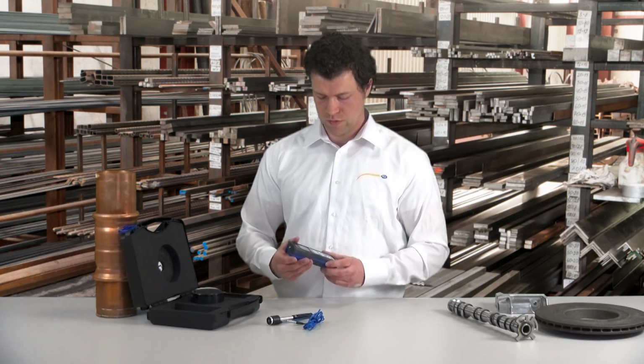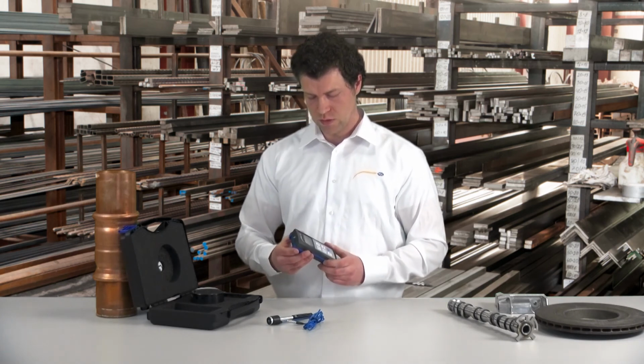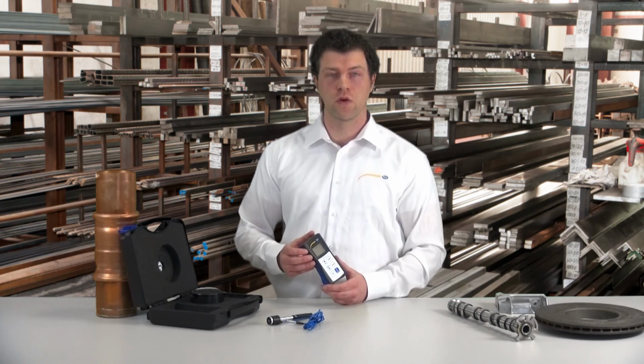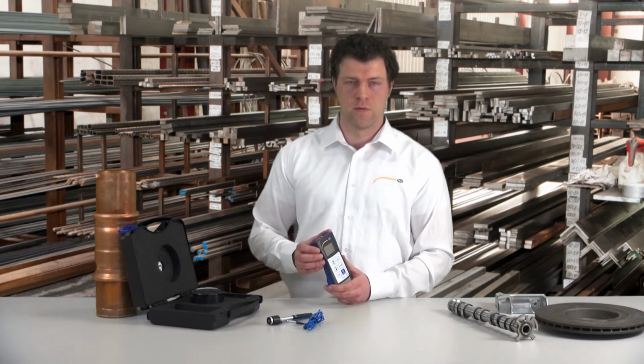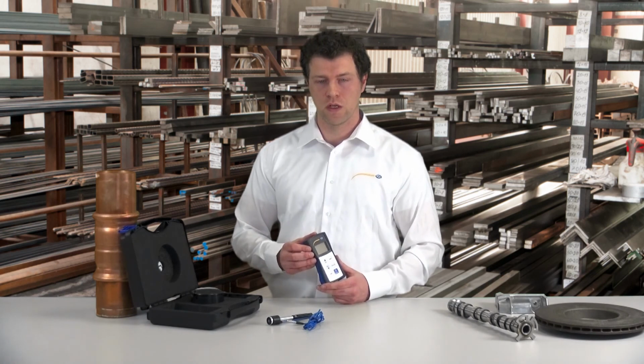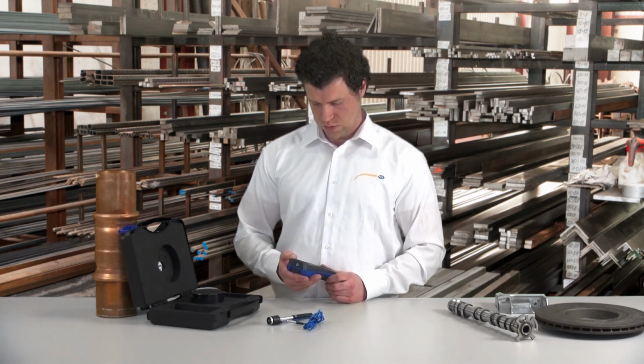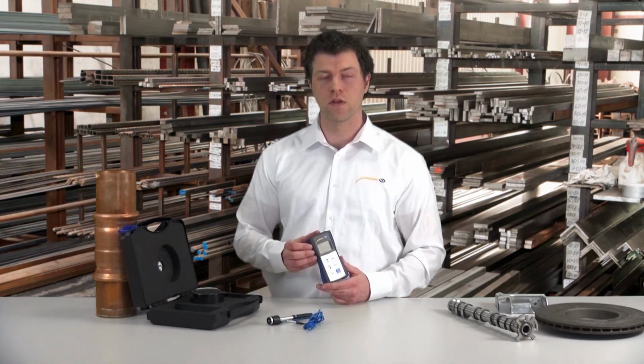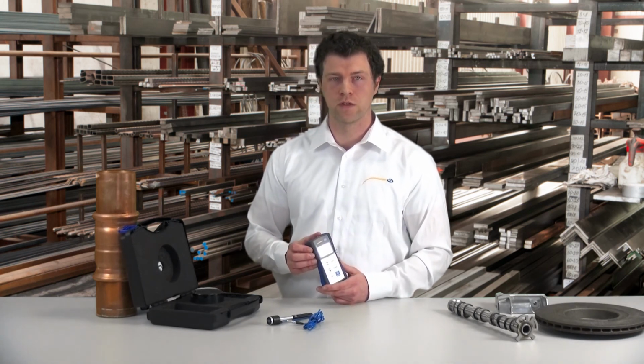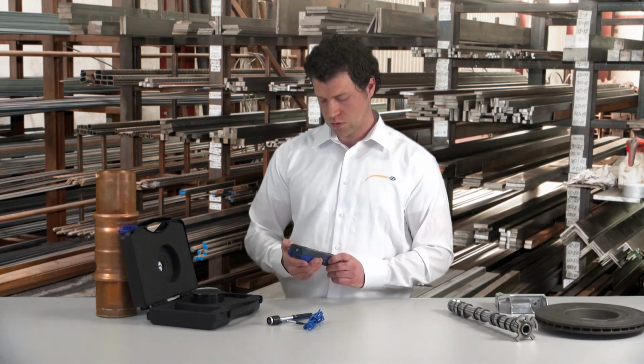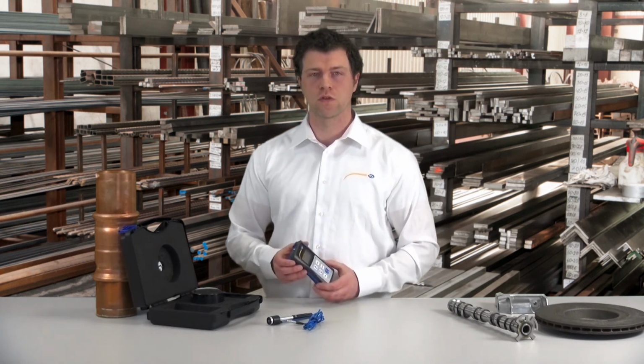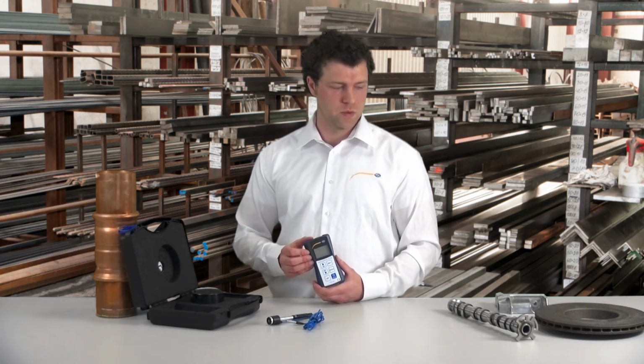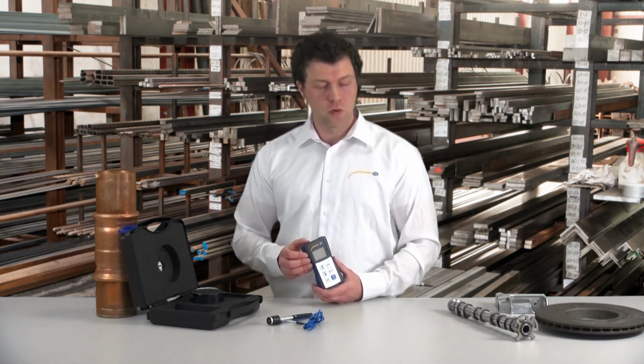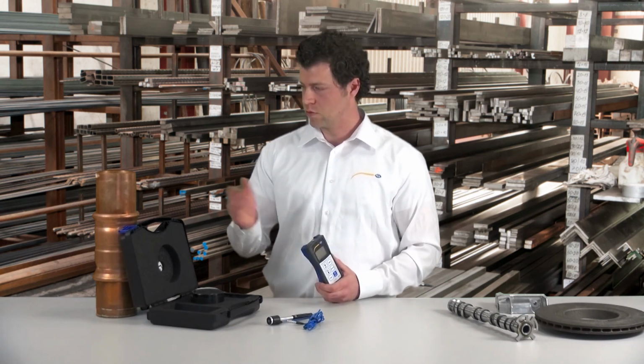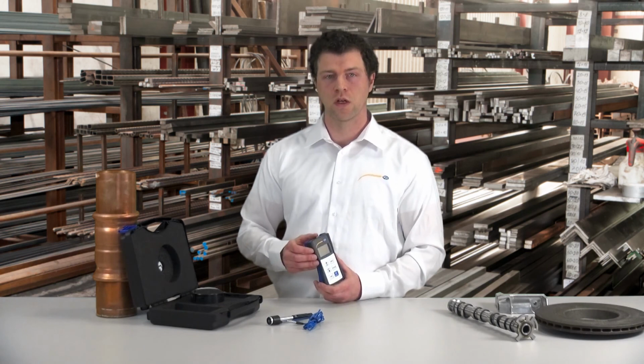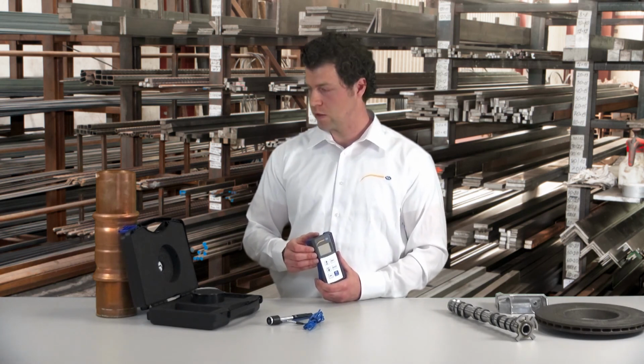The measuring device also has a ring data storage, which means the data can be stored and documented. Furthermore, there is a 232 interface, and the operation runs, as said, over 3 AAA batteries. Further equipment is also available. To this belong such things as concave adapters, when for example you want to measure round surfaces or pipes. It is useful to use such adapters because the centering of the measuring device works better.